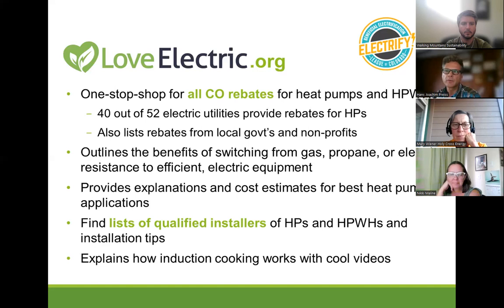In new construction, obviously, I always ask for at least 75 square feet of mechanical room for radiant. Radiant needs to go on the walls and stuff. The heat pump water heater needs some space. Ventilation system. Trying to tuck it under the stairs, that's very often what I'm being offered. Thanks, but no thanks.